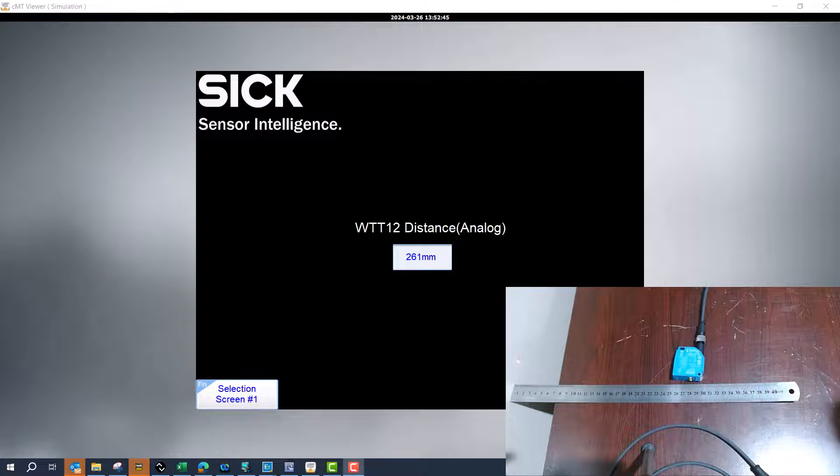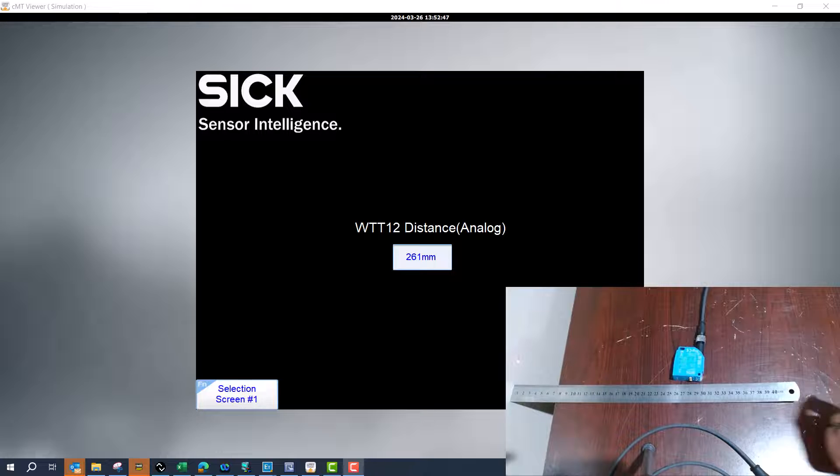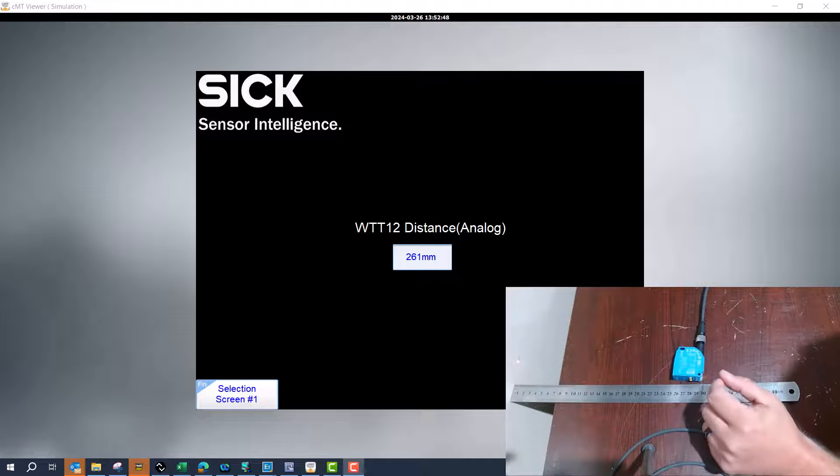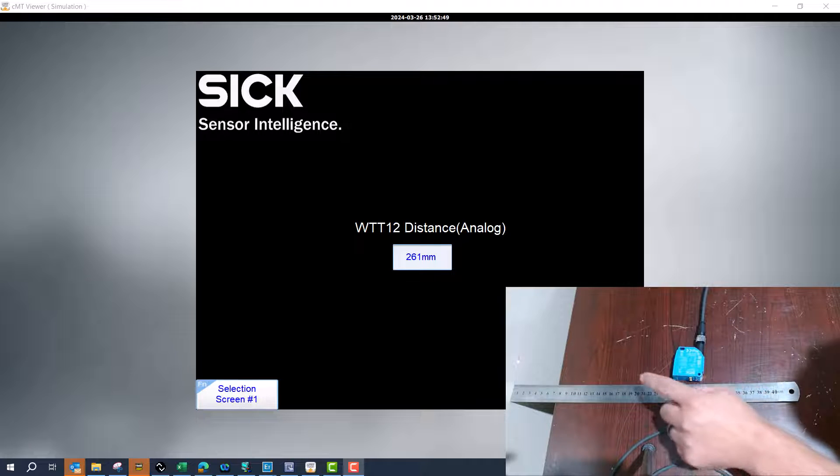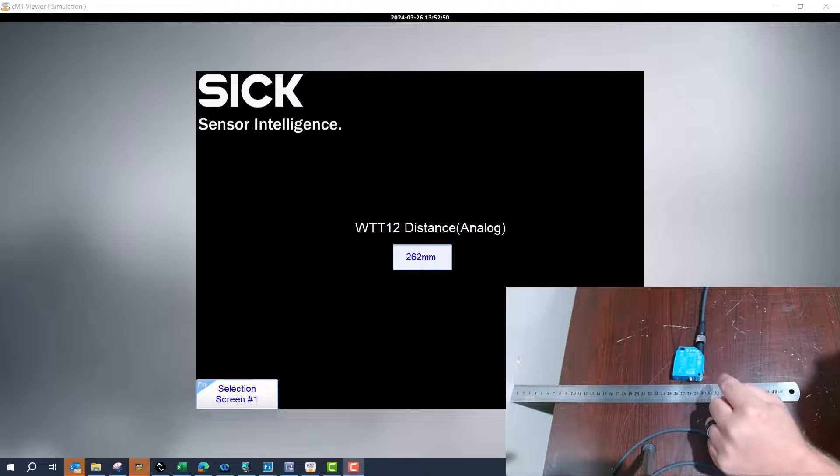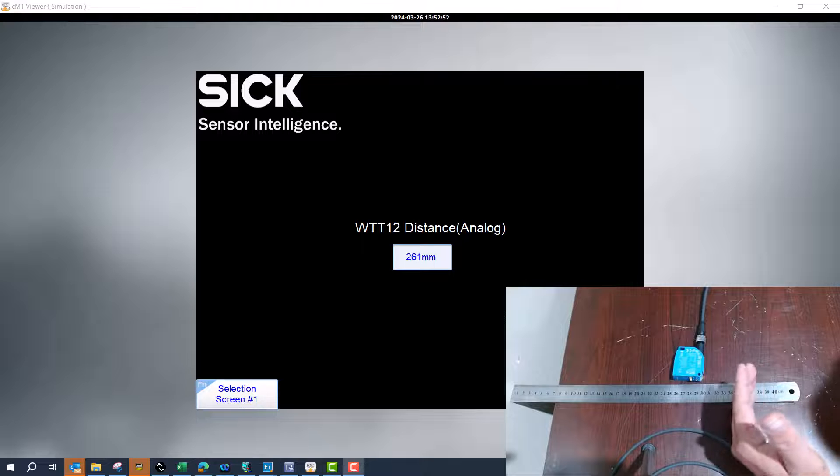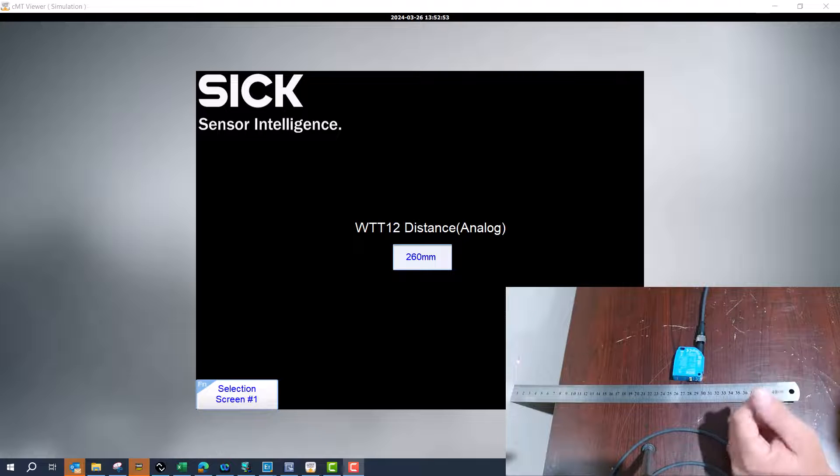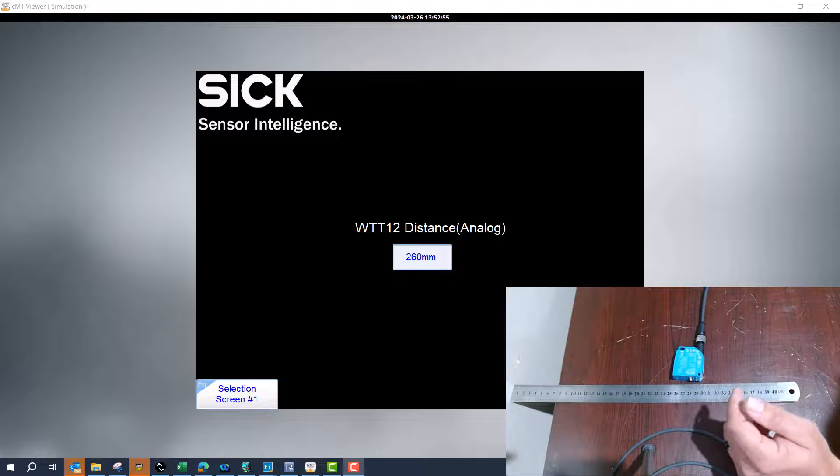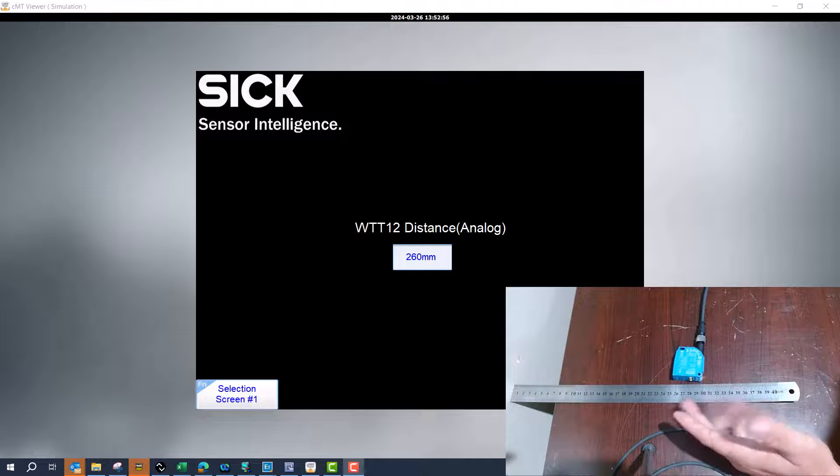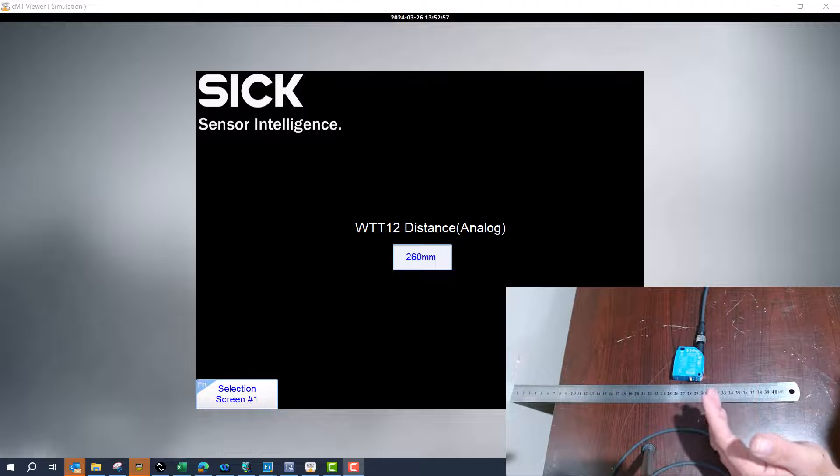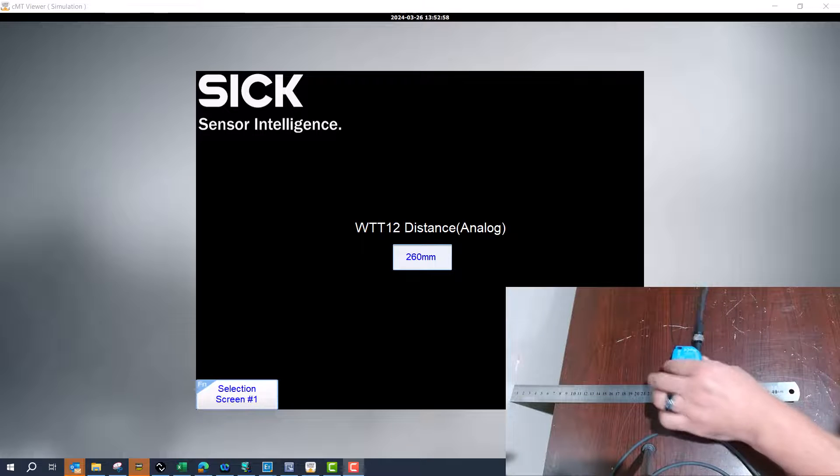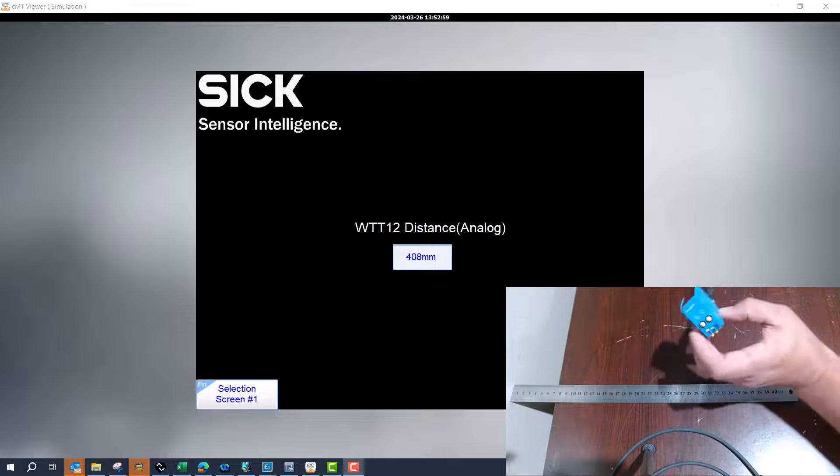So what I'm going to do is change this from 200 to 400. I'll leave the high scale side of it the same and I'll just change the bottom, but I'll have to teach both points. So first what we do, you'll see there's an analog button on the top. We'll put it at the 200 millimeter range that we want.